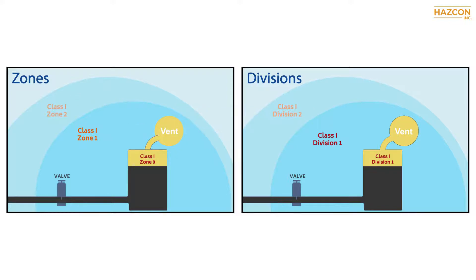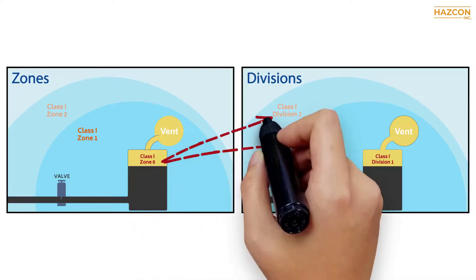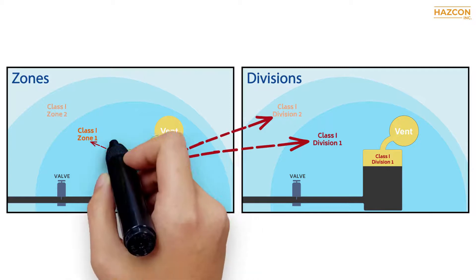Now it is time for zone certified products. Products that are suitable to be used in zone 0 may be installed in class 1 Division 1 and Division 2 and may also be installed in zone 1 and zone 2.